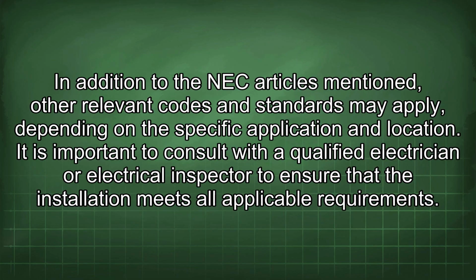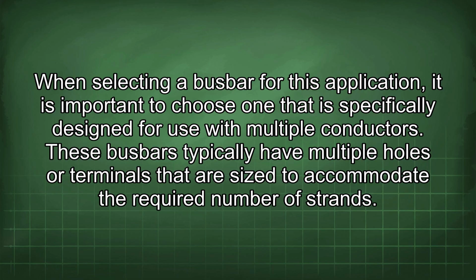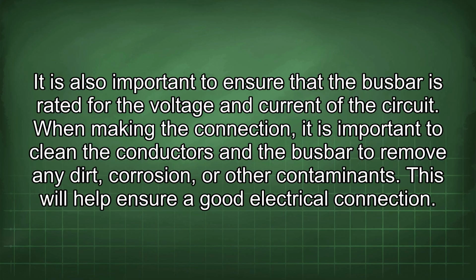In addition to the NEC articles mentioned, other relevant codes and standards may apply depending on the specific application and location. It is important to consult with a qualified electrician or electrical inspector to ensure that the installation meets all applicable requirements. When selecting a busbar for this application, it is important to choose one that is specifically designed for use with multiple conductors. These busbars typically have multiple holes or terminals that are sized to accommodate the required number of strands. It is also important to ensure that the busbar is rated for the voltage and current of the circuit.